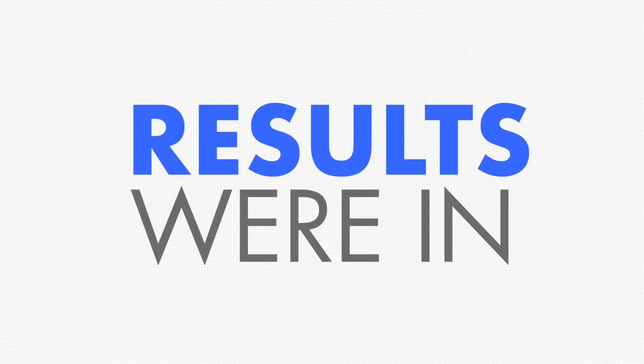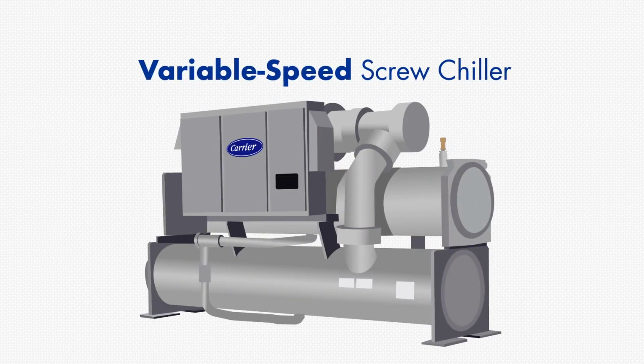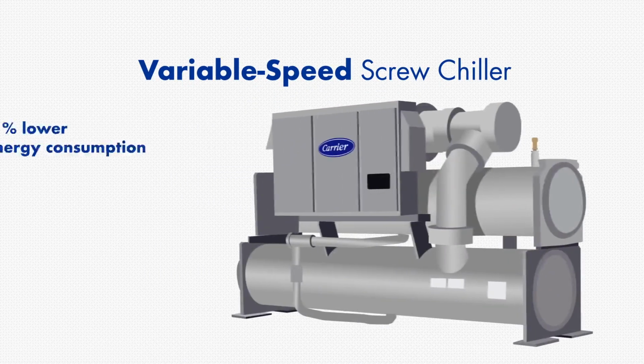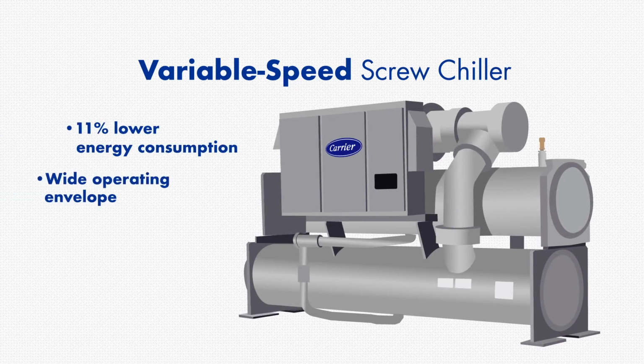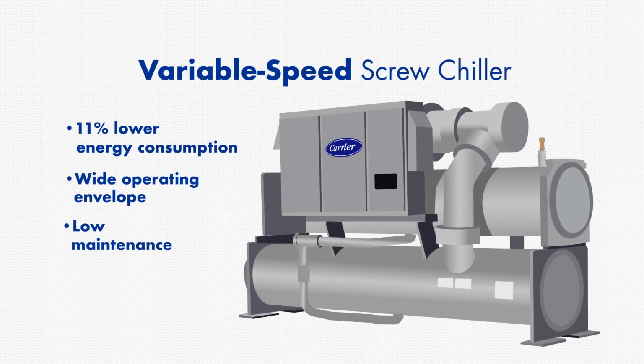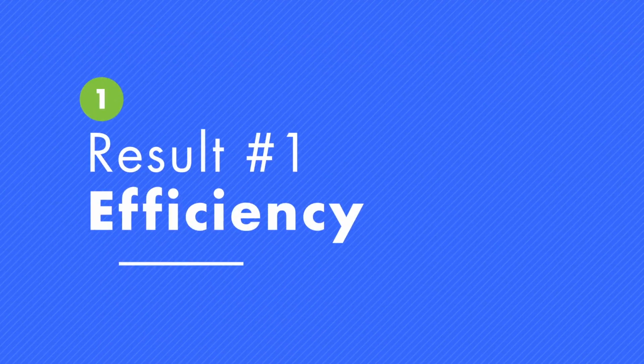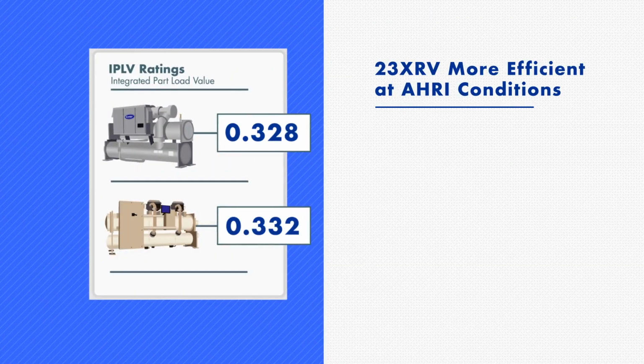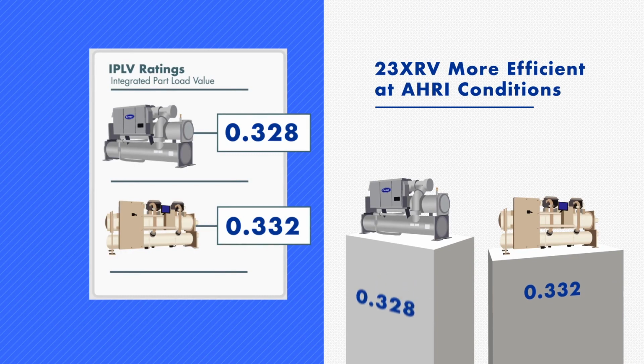After an entire cooling season of testing, the results were in, and they were significant. The Carrier variable speed screw chiller demonstrated 11% efficiency improvement over the mag-bearing chiller, with greater versatility under different operating conditions, fewer maintenance requirements, and comparably quiet performance. First, let's look at energy consumption. While the chiller submitted IPLV ratings, which are commonly referenced as an indication of efficiency, were within 1% of each other, actual results showed a much different story.